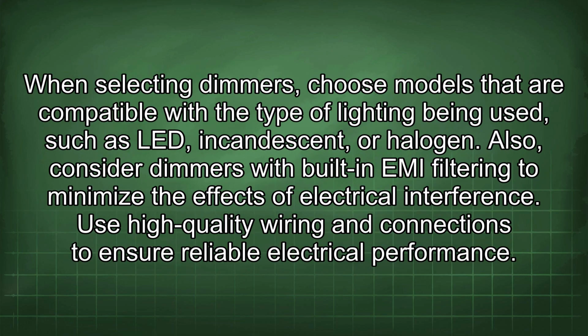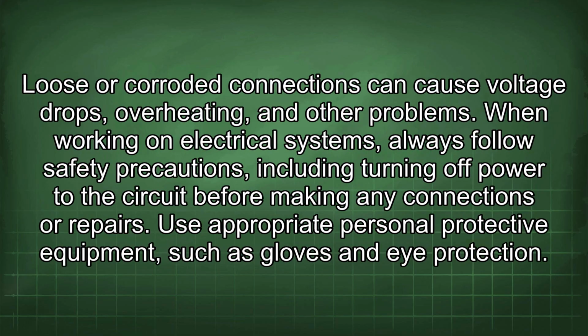When selecting dimmers, choose models that are compatible with the type of lighting being used, such as LED, incandescent, or halogen. Also, consider dimmers with built-in EMI filtering to minimize the effects of electrical interference. Use high-quality wiring and connections to ensure reliable electrical performance. Loose or corroded connections can cause voltage drops, overheating, and other problems.